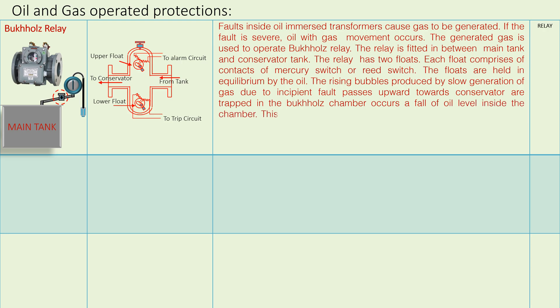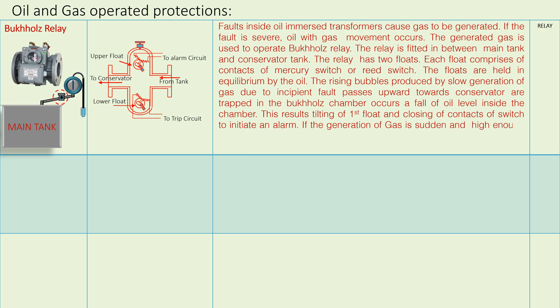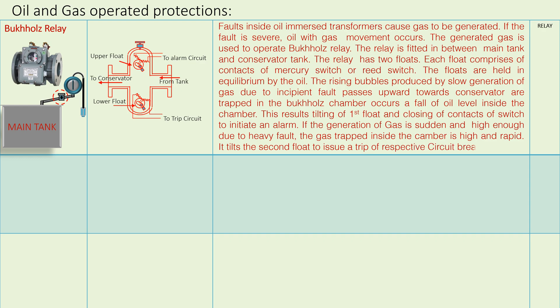This results in the tilting of the first float and closing of the switch contact to initiate an alarm. If the generation of gas is sudden and high enough due to a heavy fault, the gas trapped in the chamber is high and rapid, causing the second float to trip the respective circuit breaker of the transformer.